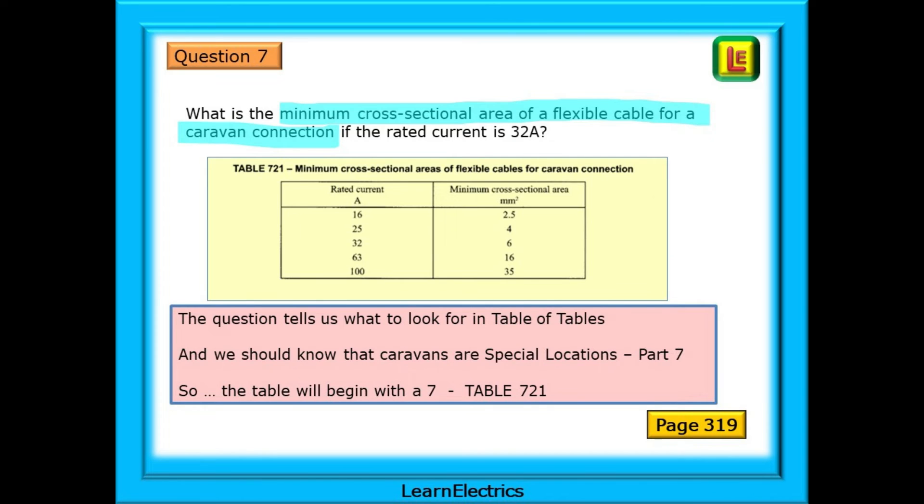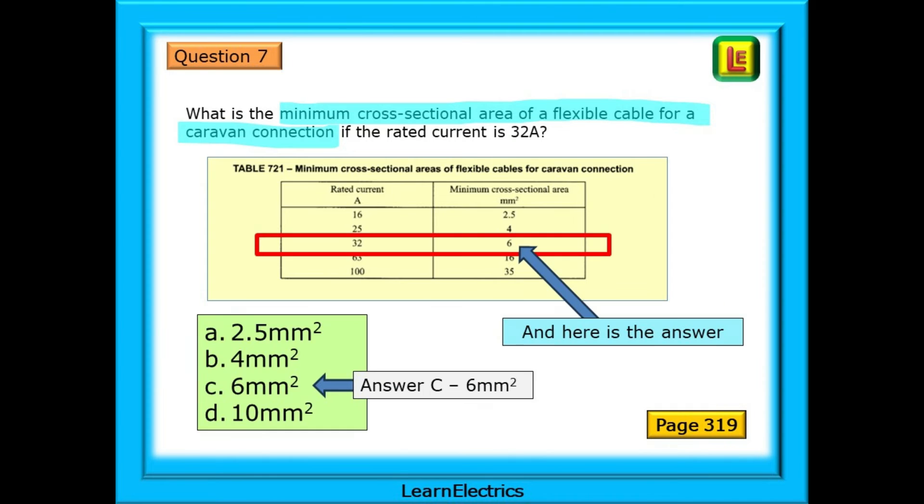The question tells us what to look for in the table of tables at the back of the book. And we should know that caravans are special locations, part 7. So, the table will begin with a 7. Table 721, and we find this table on page 319 of the book. It is now a simple case of finding 32 amps in the left column and matching this to the right column. And here is the answer, 6 square millimetres. Answer C. So easy with the right table selected.